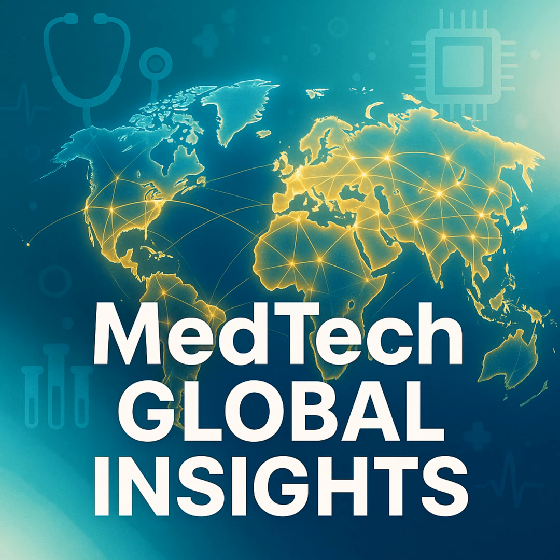The entire 510(k) process hinges on one key concept: substantial equivalence. You must prove to the FDA that your new device is as safe and effective as a legally marketed device, known as a predicate. The first and most critical mistake companies make is selecting the wrong predicate.